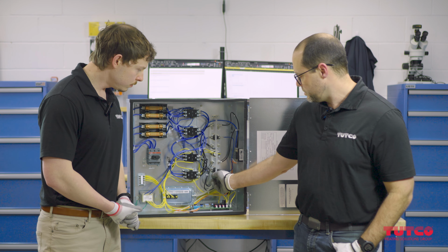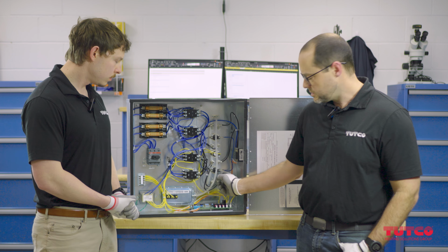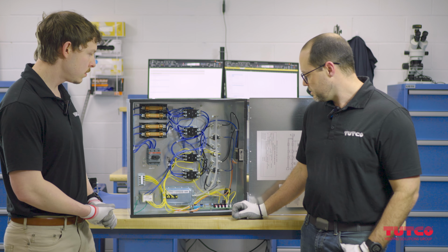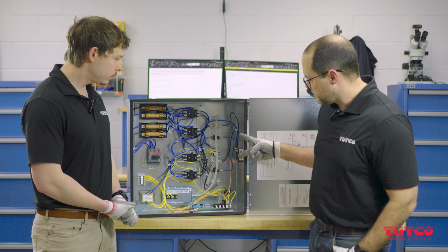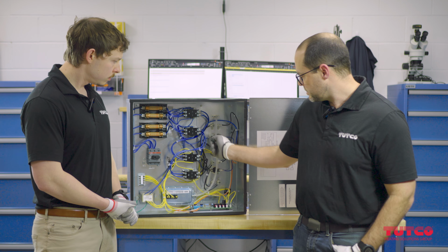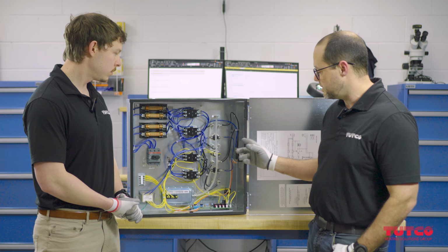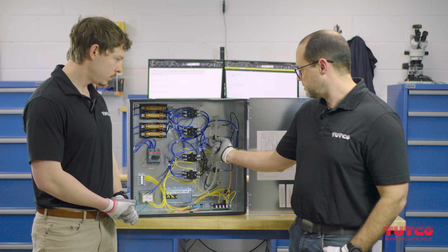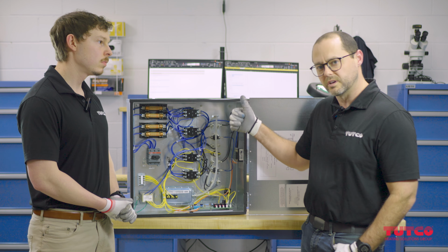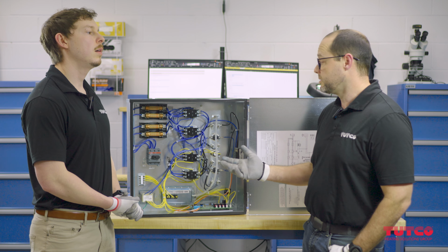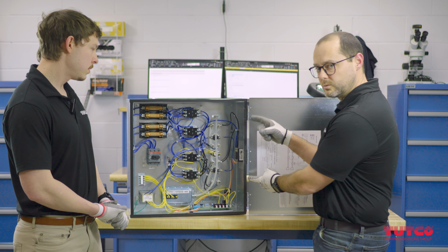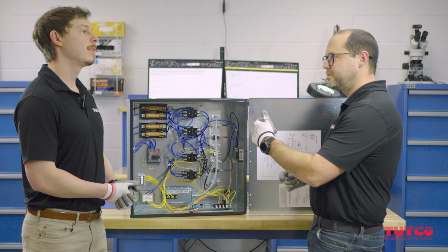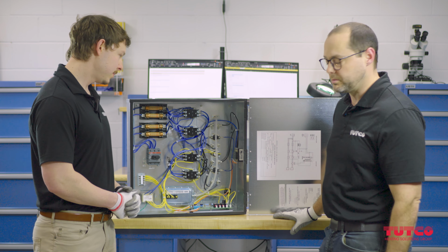This one has 2 manual limits and 1 auto reset limit. We put limits on either side, hence the flippability. Before the E-Series, there was only 1 manual limit, and it always had to be at the top. On the E-Series, we put 2 manuals, so one's always on top whichever way you flip it.